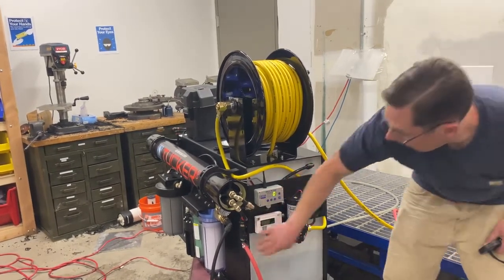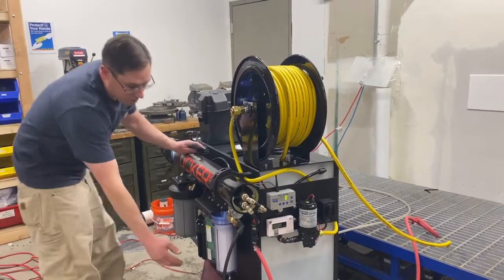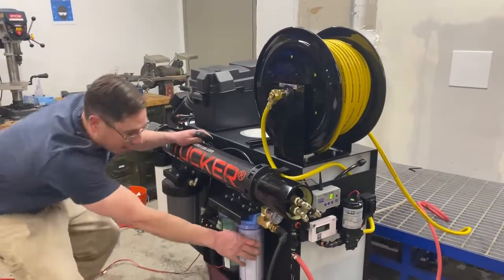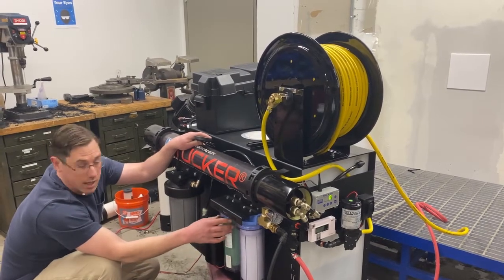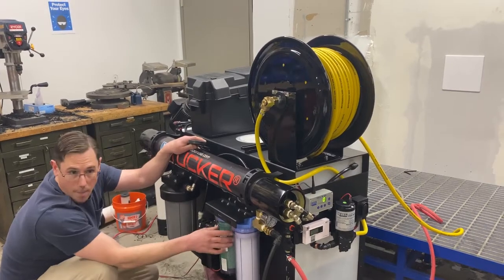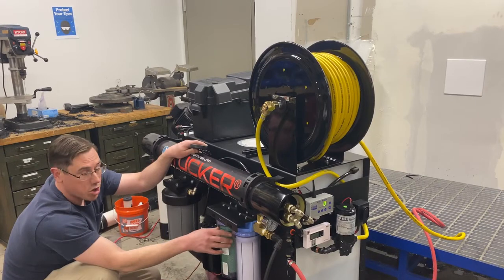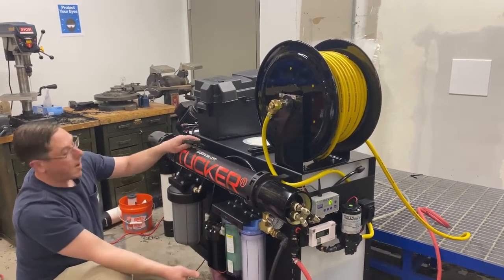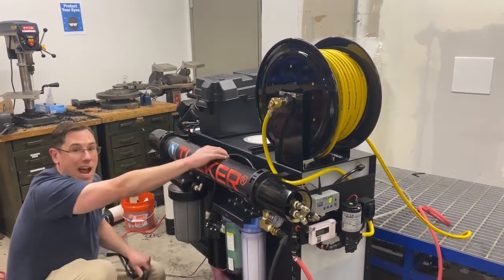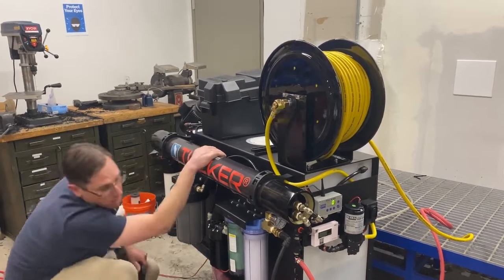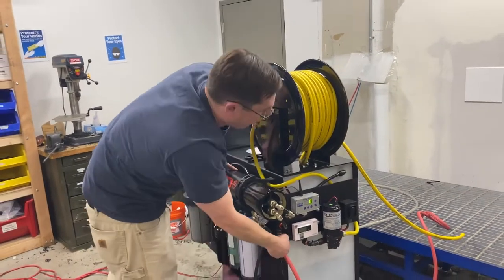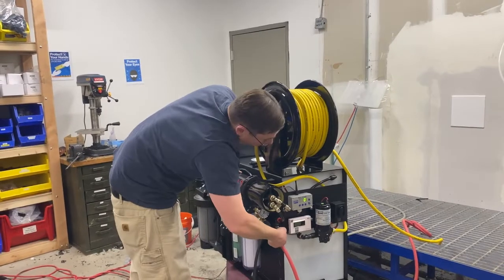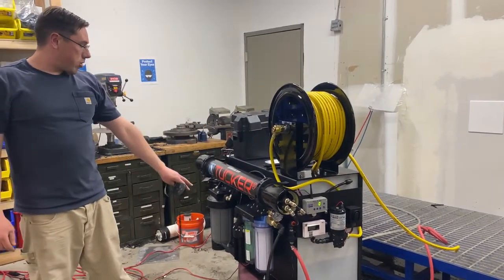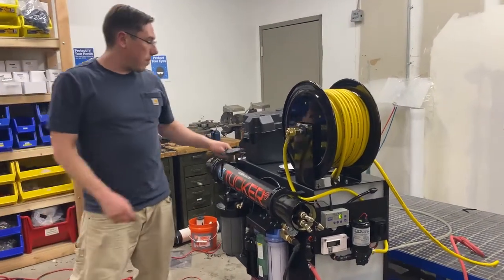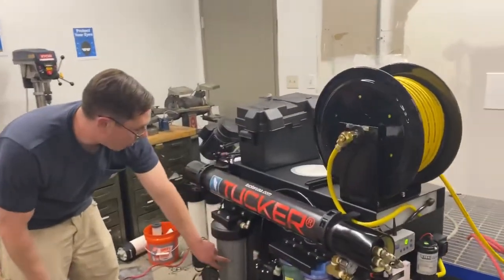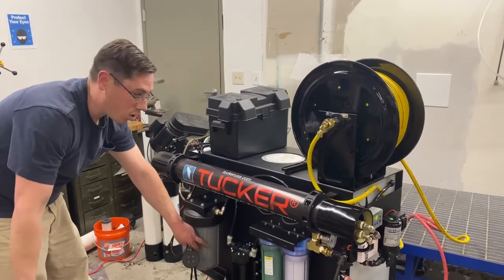This is currently in flush mode, and after your pre-filtration, which consists of your sediment filter to catch heavy rust and particulate, your carbon filter, which will either de-chlorinate the water to protect your RO, or these catalytic carbon filters will remove chloramines, which your municipality may be using to disinfect the water. Here's your reverse osmosis membrane. It's going to do about 90% of the purification, and it'll also produce a waste stream. At your RO, you will have a bypass valve to either run in a flush mode, as it is now, or close that down. You can hear the boost pressure come up through the booster pump, and it's going to start making water into the tank. After RO, you have deionization filtration, which is going to bring it down to 100% pure.